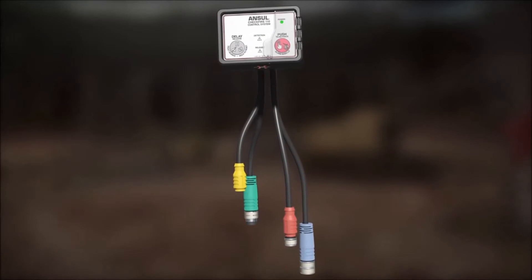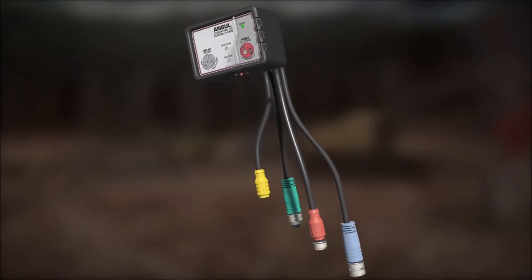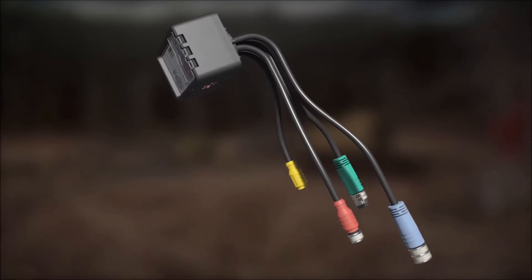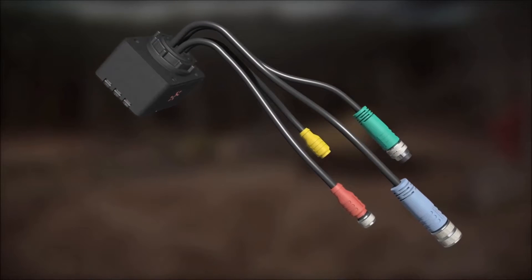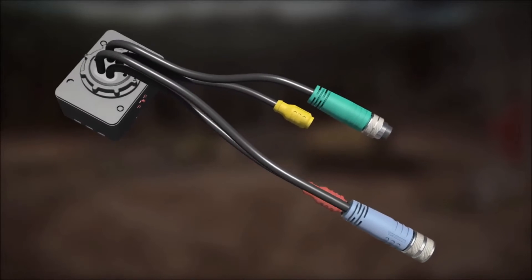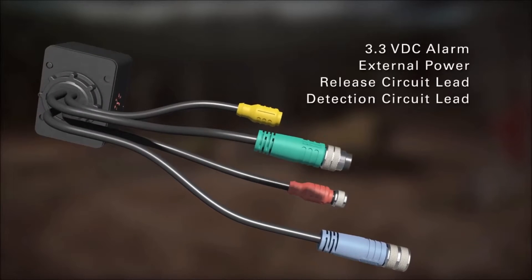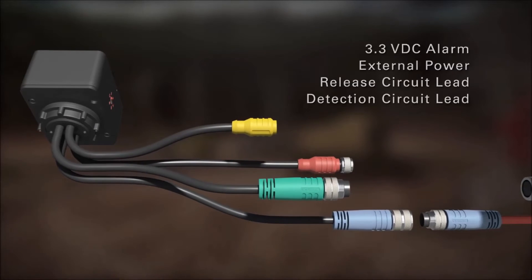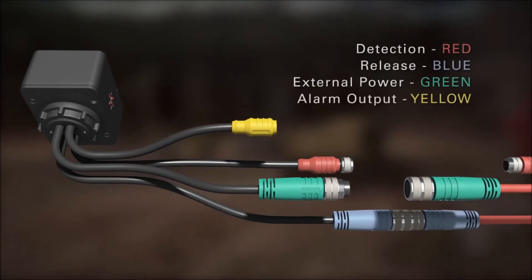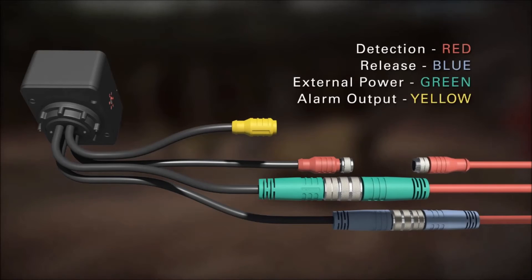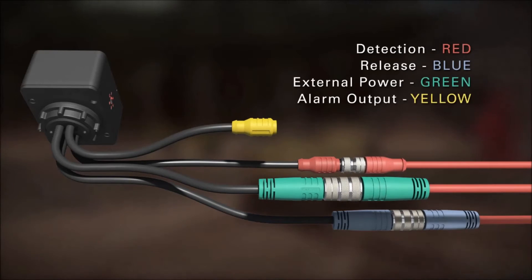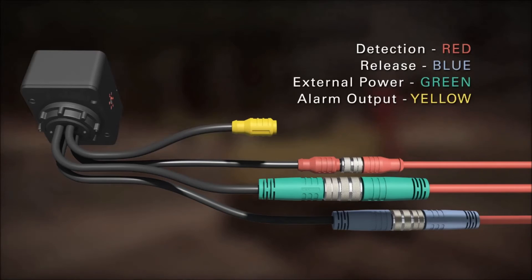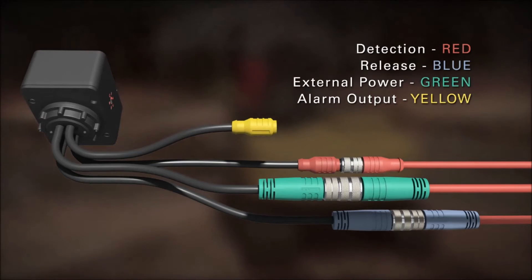The CheckFire 110 system utilizes IP67 circular threaded connectors on all cables and components. These dust and watertight cable harness connections help protect the detection and actuation system from rigorous operating and environmental conditions. All cabling is plug and play with color-coded over-molded connectors and corresponding colors for ease of installation and replacement in the event of damaged cables.